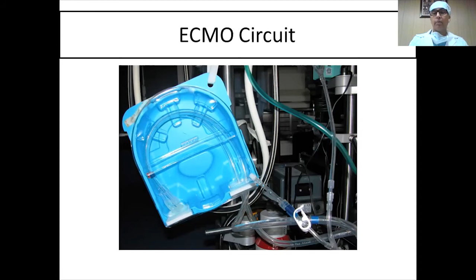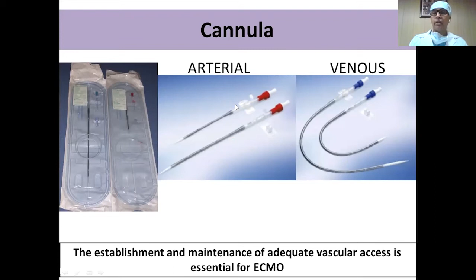These are the cannulas, which are advanced cannulas that can help with percutaneous placement. You can see on the right-hand side the venous cannula, which is the longer one, and the arterial cannula. These are the return cannulas, and these are the smaller ones. These are available in different sizes depending upon the patient's age and weight. We decide about the cannula for getting access on the venous side and for returning on the arterial side. Cannulation is the most important step during the ECMO procedure, because if your cannulation fails or is not correct, you can never initiate or run ECMO for any patient. So this is how the line looks. You can see this is the venous head where the blood is coming.